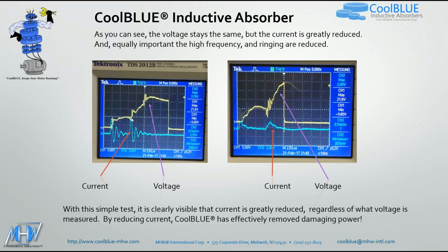Here we're up at almost two divisions. That's been reduced down to about 3/4 of 1 division. So this was done strictly with the Rogowski coil, which is available through DREISILKER. With this simple test, it's clearly visible that current is greatly reduced, regardless of what the voltage is measured. By reducing current, CoolBLUE has effectively removed the damaging power.